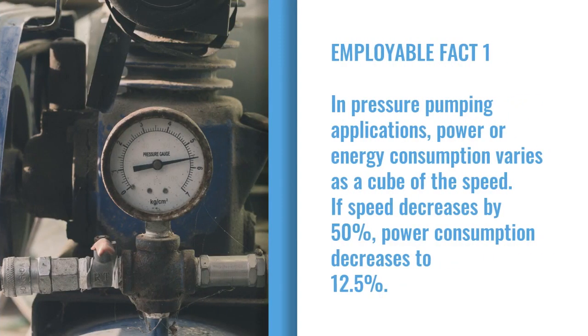Employable Fact 1: In pressure pumping applications, power or energy consumption varies as a cube of the speed. If speed decreases by 50%, power consumption decreases to just 12.5%.